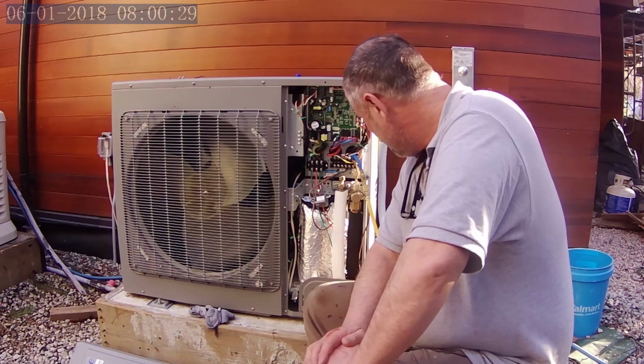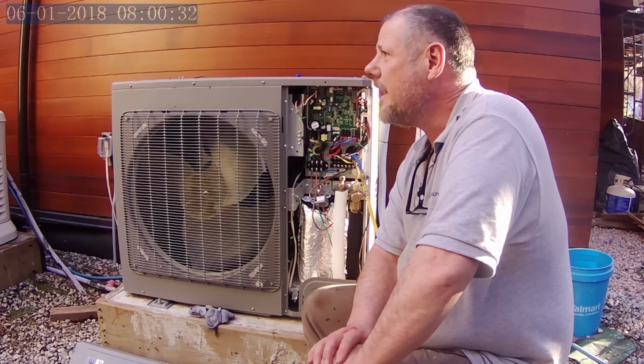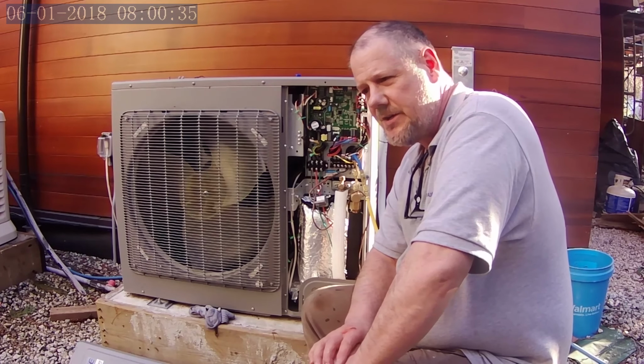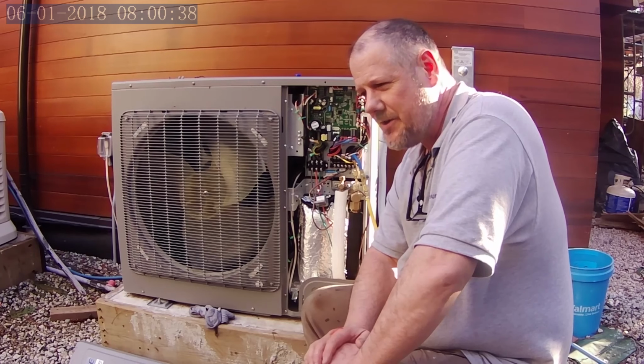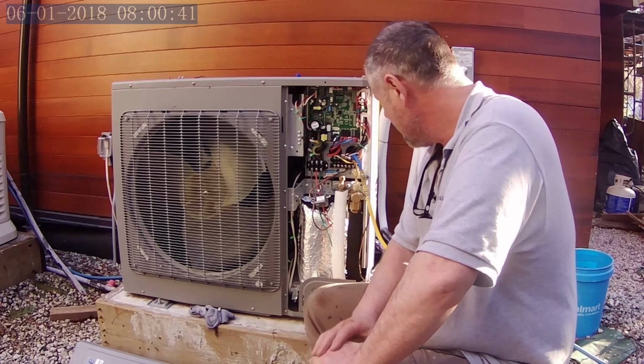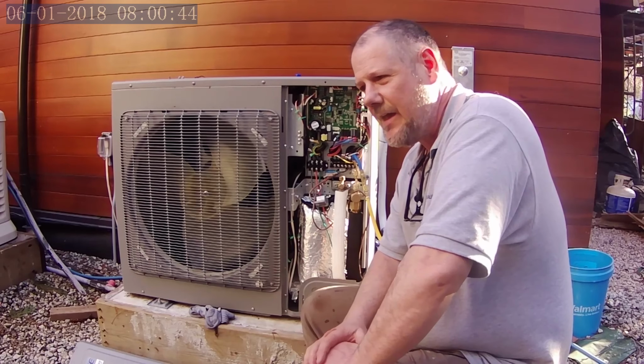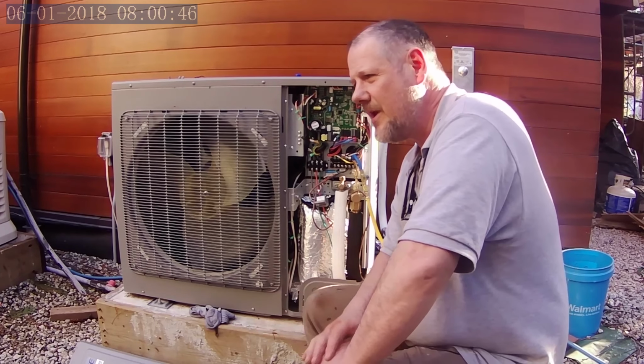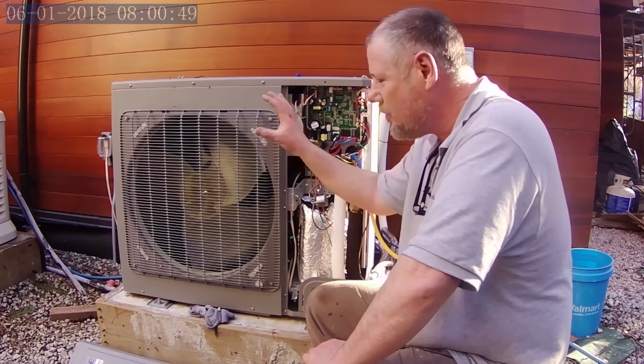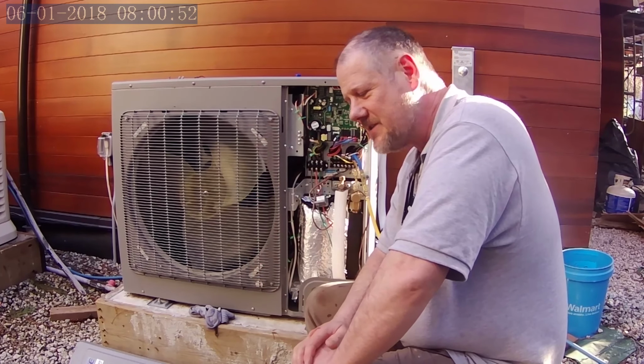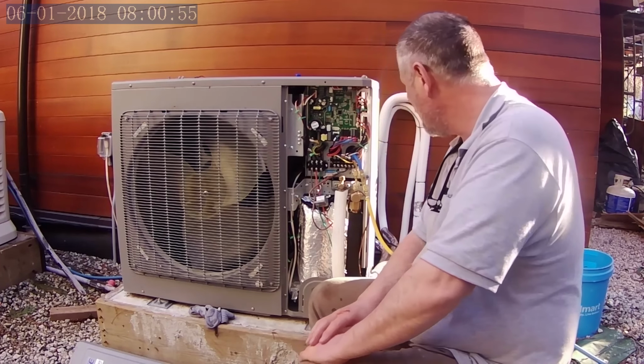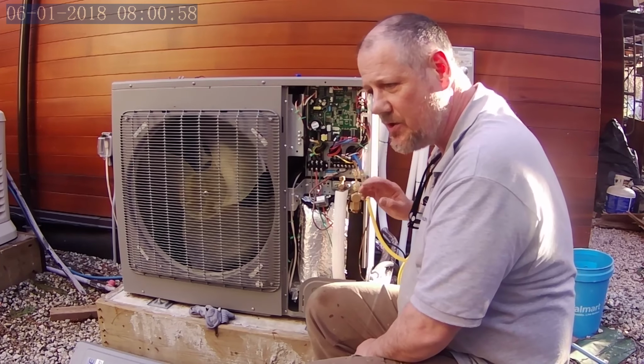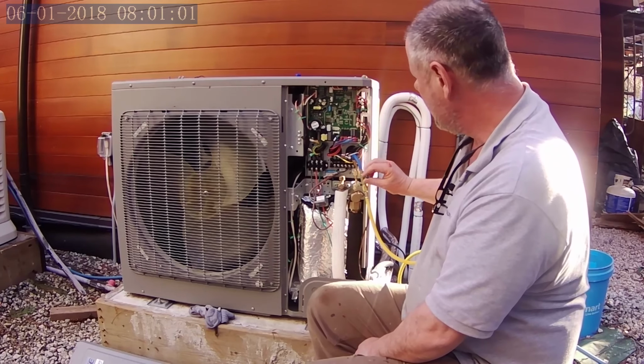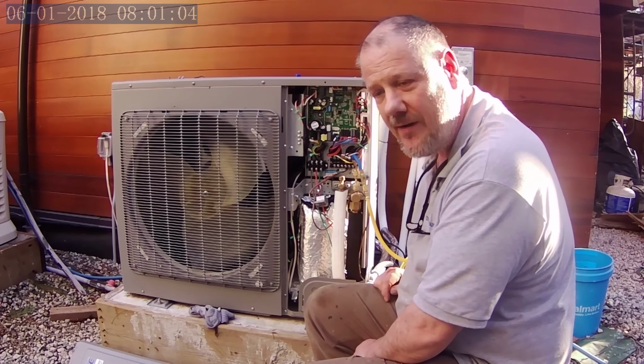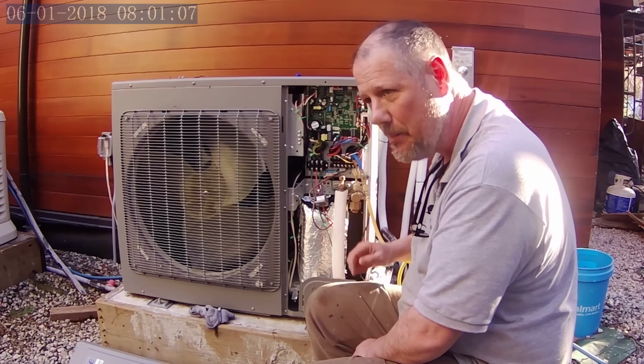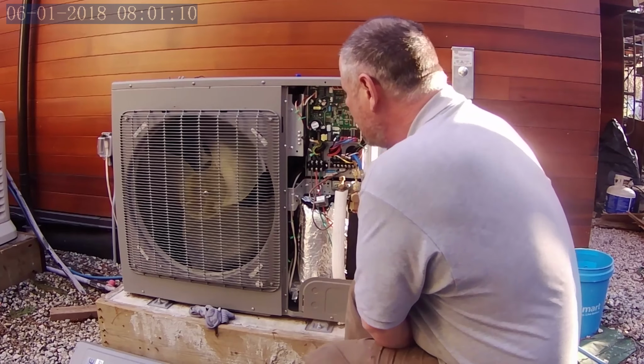Okay, we've had the vacuum pump running most of the day. Not sure if we got to 500 microns or not, but we're not sure whether or not the inside sensor doesn't really do negative values that well. But when we had the manifold gauge on, it was pegged at minus 30 psi. So we should be okay. I've also had the vacuum pump off and isolated for the last half hour, and the pressure hasn't decayed. It hasn't gone up at all. So we should be good.